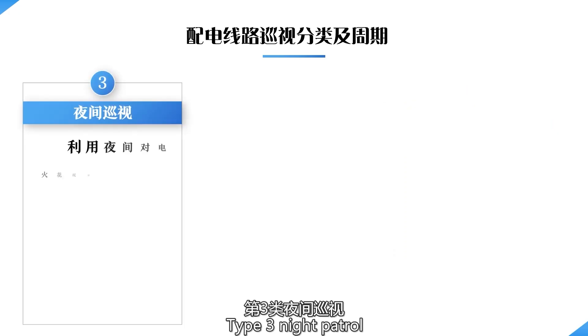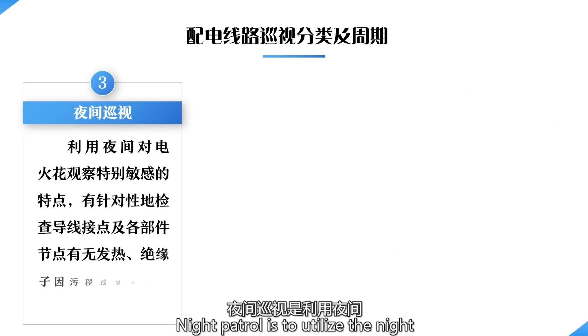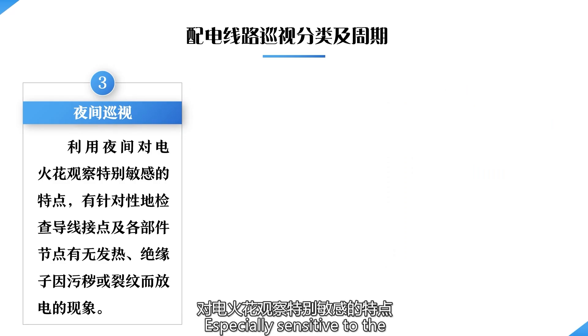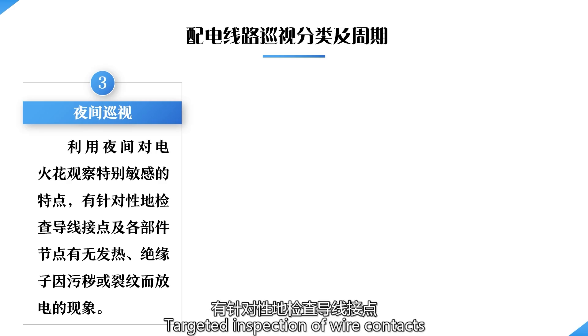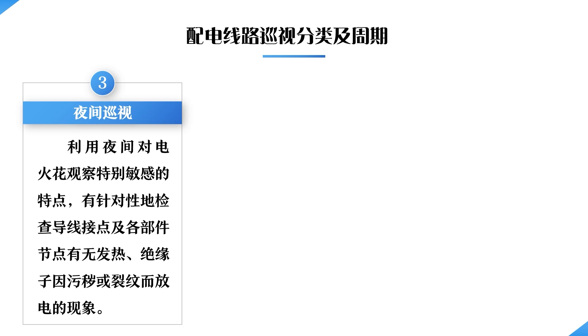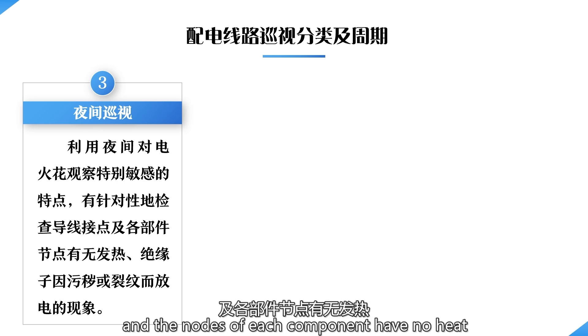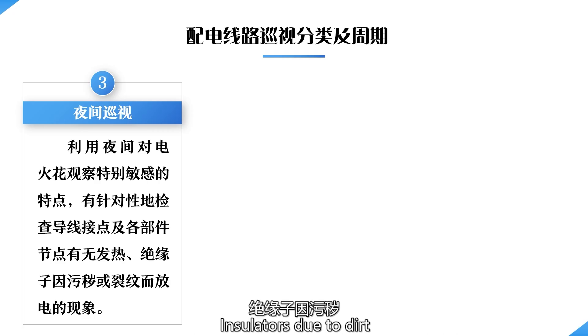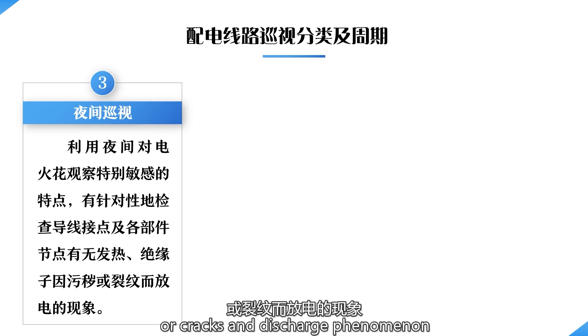Type 3 is night patrol. Night patrol utilizes nighttime conditions, especially the sensitivity to spark observation, for targeted inspection of wire contacts and the nodes of each component to check for overheating, and of insulators for dirt, cracks, or discharge phenomena.